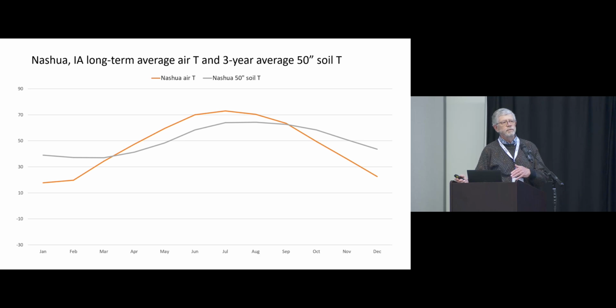So at 50 inches, the difference between the high temperature and the low temperature 6 months later is about 30 degrees. If you go down to 8 feet, it'll be about 20 degrees. And then if you go down to 15 feet, it shifts later yet, and the peak, rather than occurring in July like the air temperature peak, it'll occur about the beginning of November, which corresponds to the beginning of heating season. So the amplitude at that time, at 15 feet, will be only 5 or 6 degrees above the average temperature, and then 6 months later, 5 or 6 degrees below.